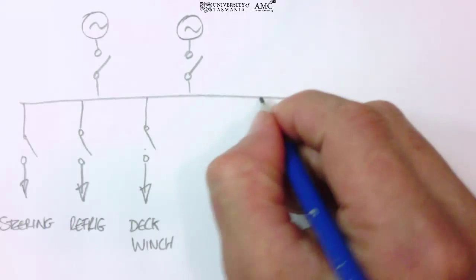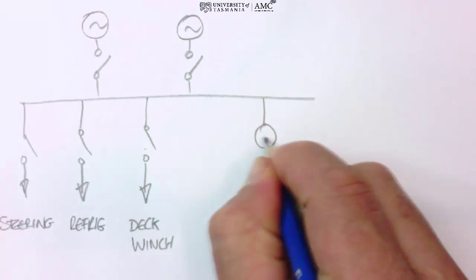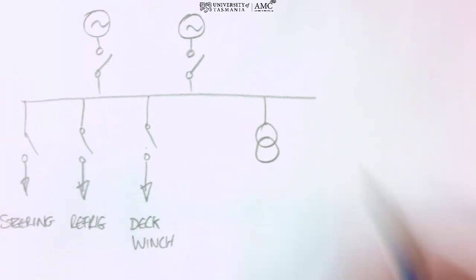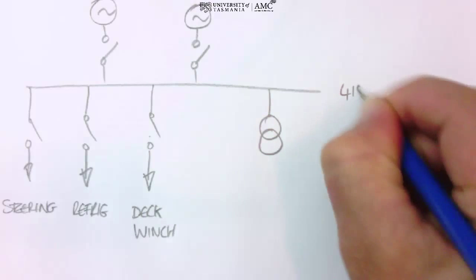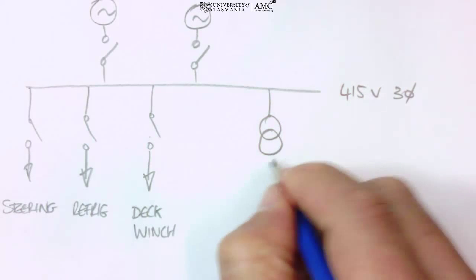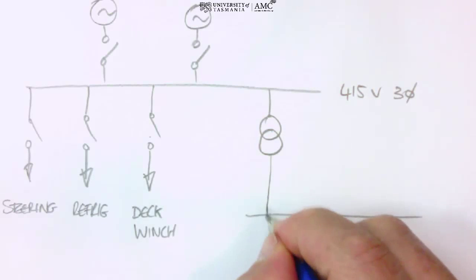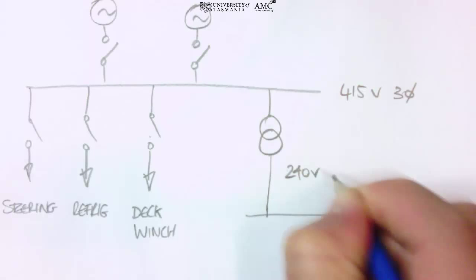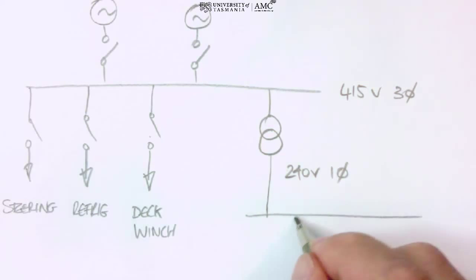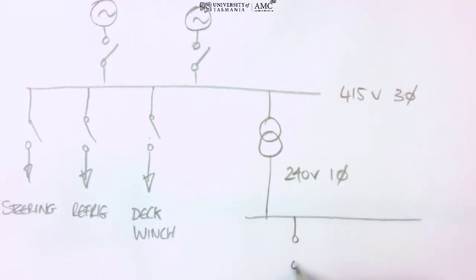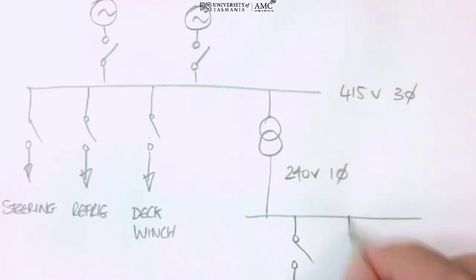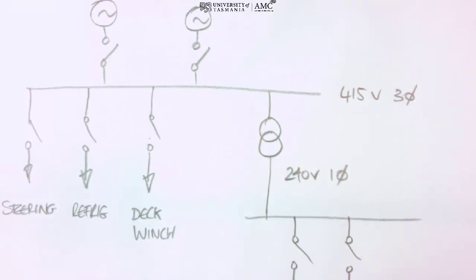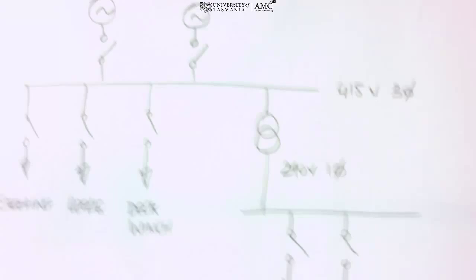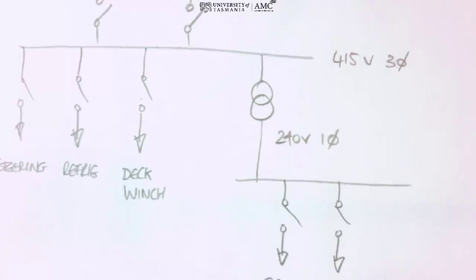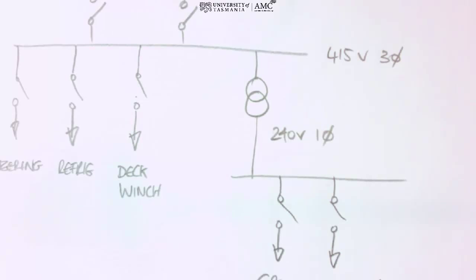Okay, now we are also going to have a transformer. So this is all along here is 415 volts, 3-phase. So after our transformer we transform down to 240 volt single phase system, and from here draw in some circuit breakers, and here's our single phase load down to our general purpose outlets or power points, and things like our lighting, any other single phase load consumers for cabins.